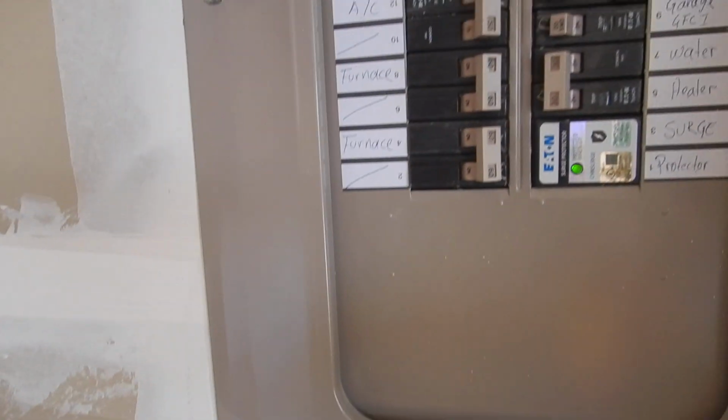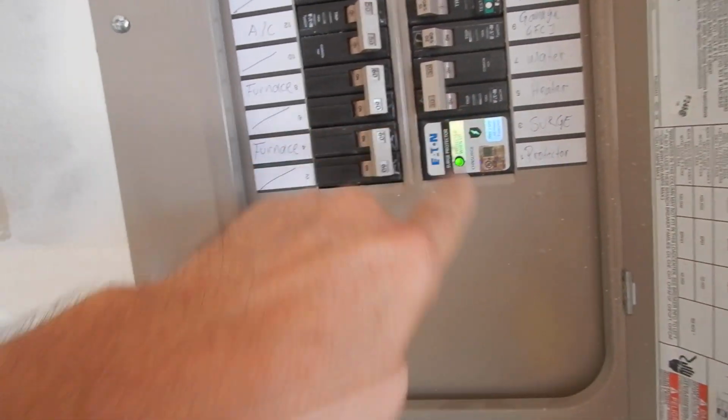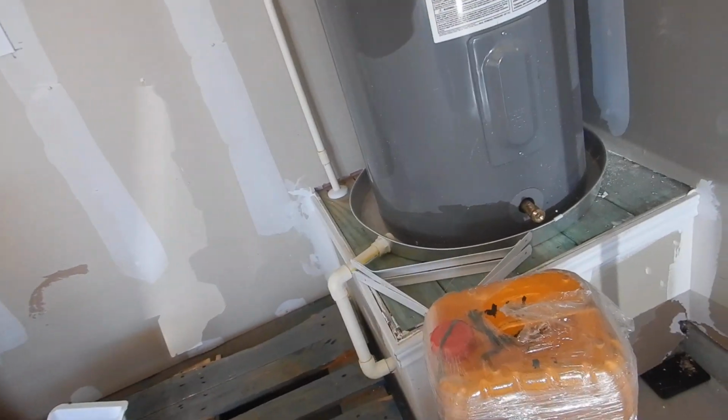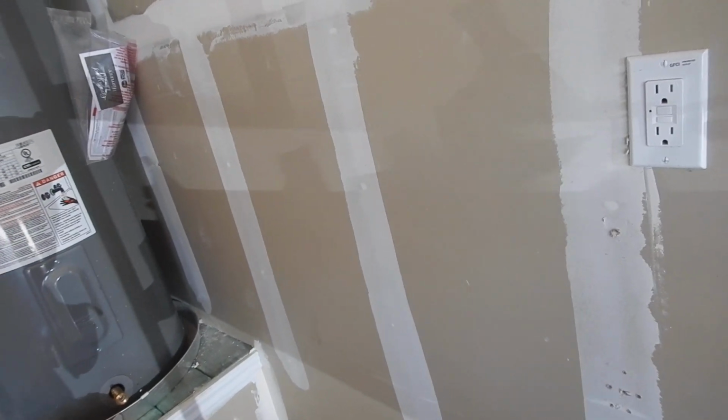This is our water heater. This is our care and use manual. There's some things going on with our water heater. One, it's not GFCI protected. All right? Water heater, not GFCI protected. Now here's another thing. There's some controversy. I'm okay with this, but I want to address the controversy in case it comes to light. You're supposed to have a switch within 6 feet. I'm not a tall man. Within 6 feet of the water heater.